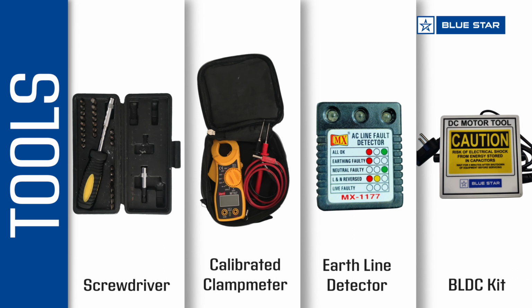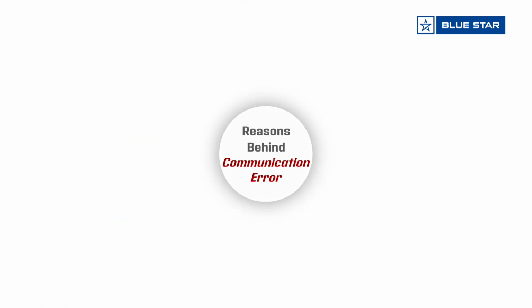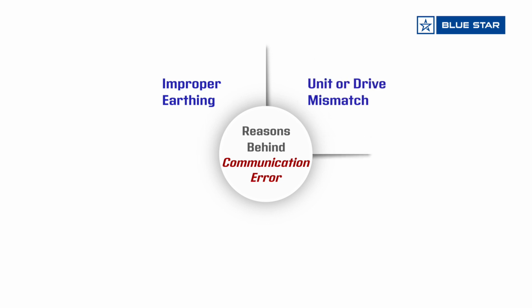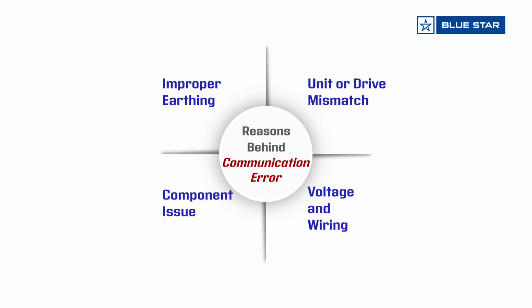Before we start with the troubleshooting process, let's understand the reasons behind the system showing communication error. Improper earthing to the unit is the very first reason of communication error. In case of unit mismatch, it shows communication error. Voltage or wiring issue is another reason. Apart from these reasons, failure of some components also leads to a communication error. The components are ODU drive and IDU PCB, DC reactor, fan motor, and compressor.